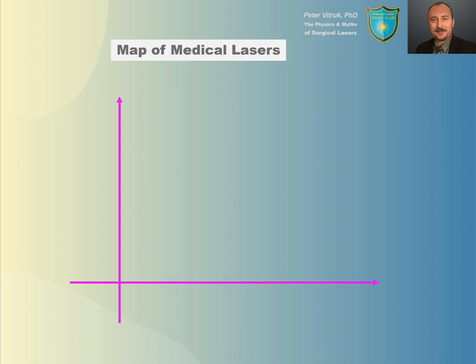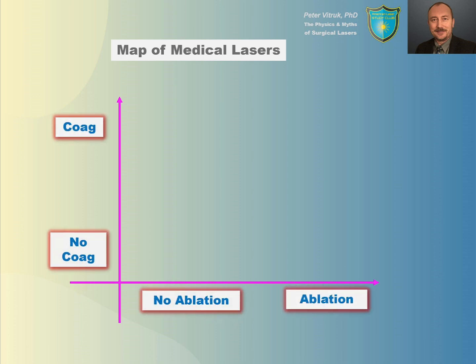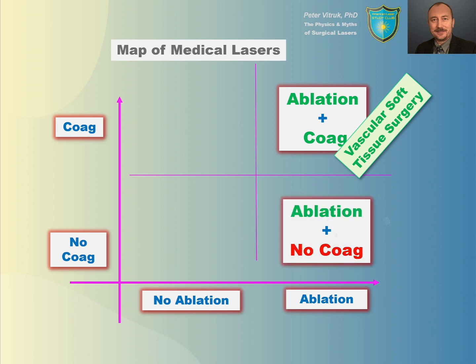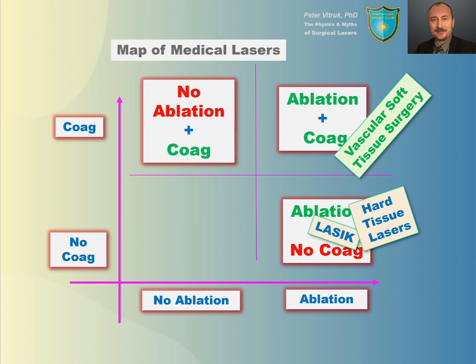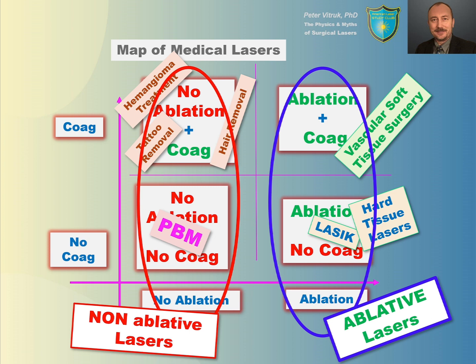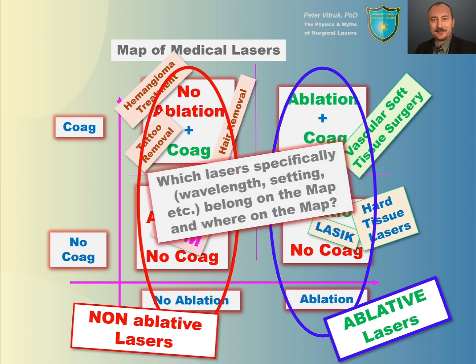We recognize that there are lasers out there that do not cut and do not coagulate. Here is a simple map of all lasers from the perspective of their ability to ablate and coagulate. Top right corner: ablation and coagulation — perfect for vascular soft tissue surgery. No ablation but with good coagulative properties — perfect for those applications. Photobiomodulation lasers do not inflict much thermal effect. Ablative lasers are on the right, non-ablative on the left.